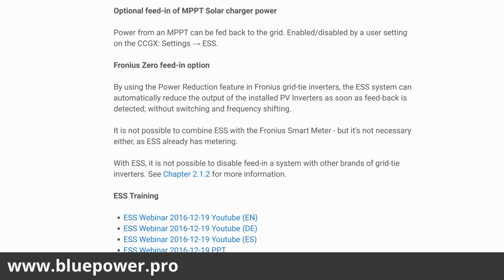So in this scenario, we can achieve zero consumption by just setting up the communication between the Victron and Fronius grid. So it is not possible to combine ESS with a Fronius smart meter, but it's not necessary either, because you can achieve the zero feed-in with a Victron energy meter if you do want to feed in or feed loads before the inverter from your Fronius inverter.